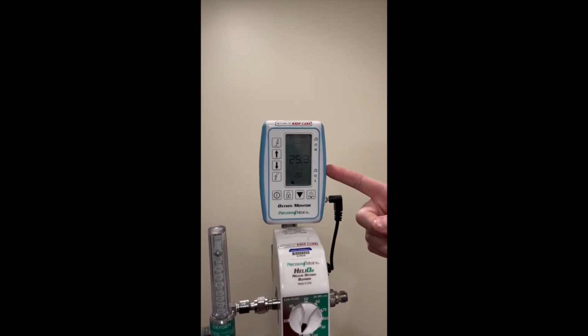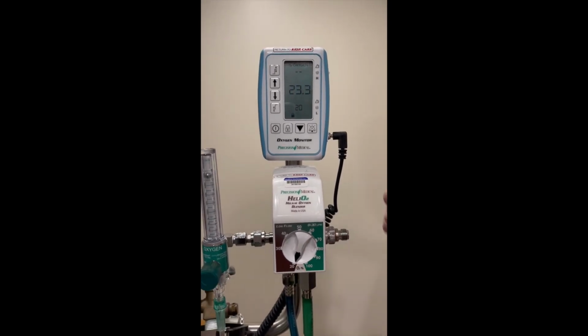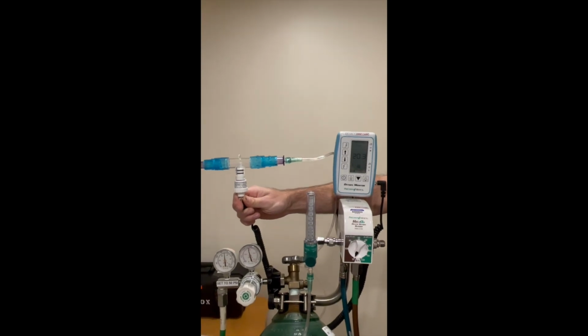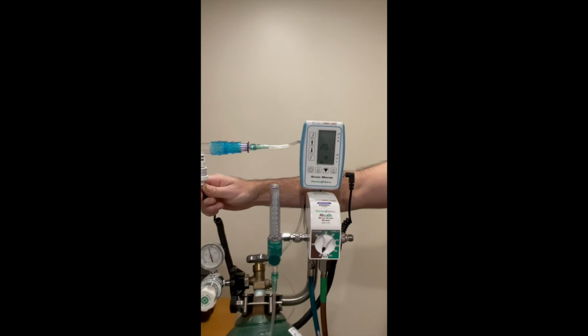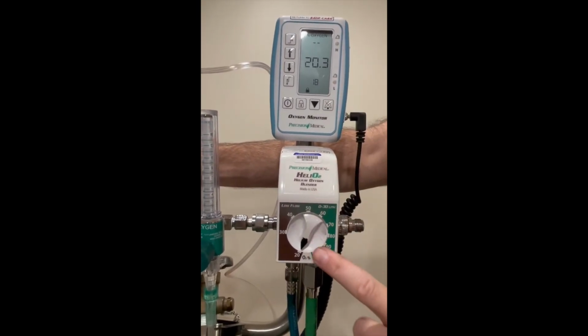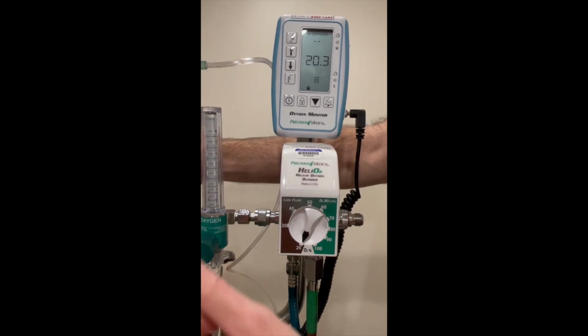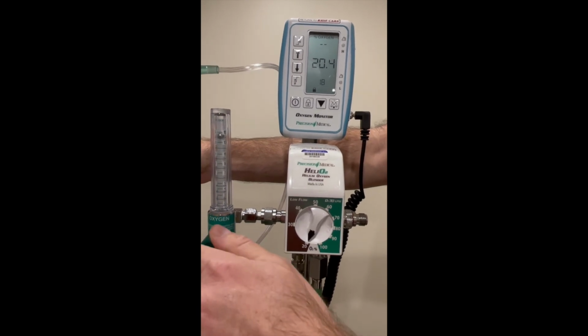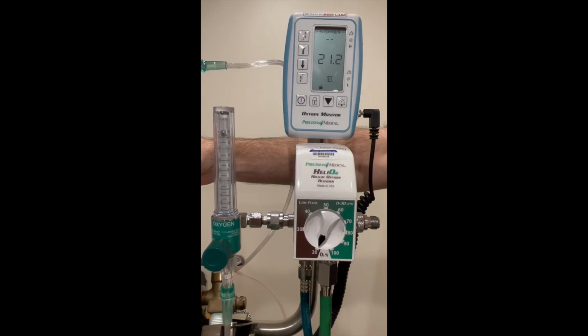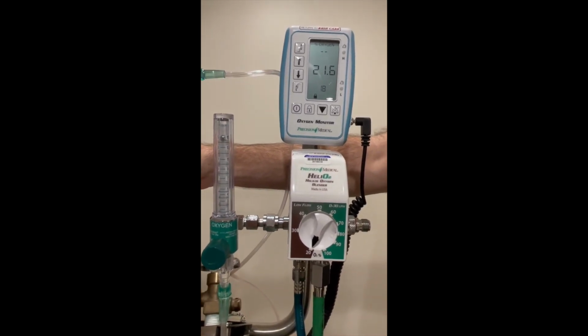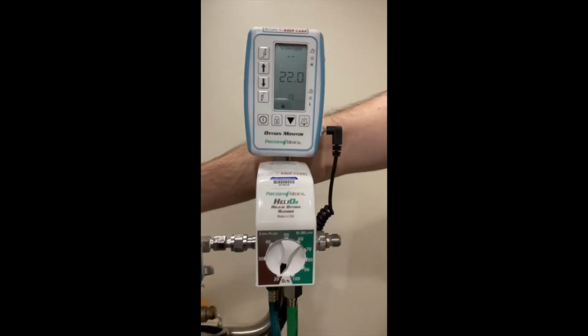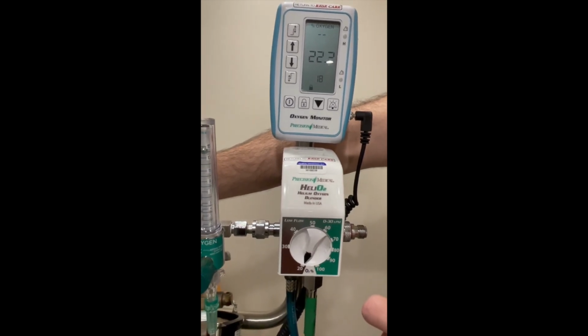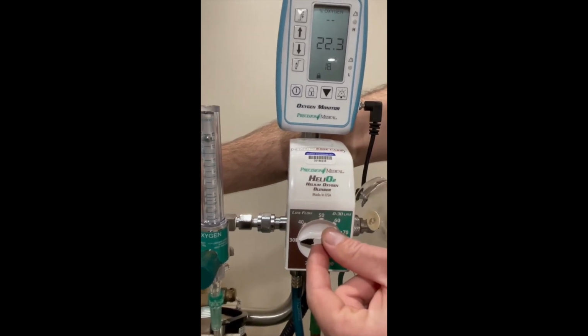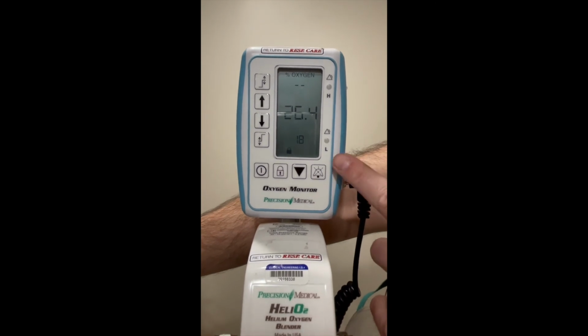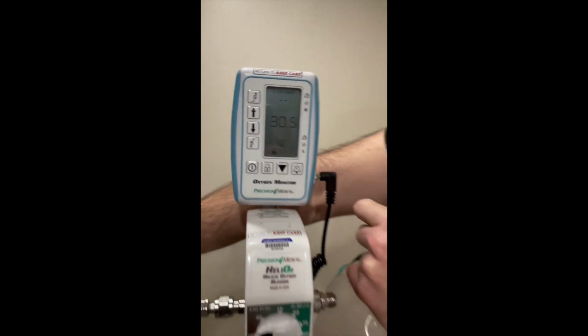You can turn on your analyzer to notate the amount of oxygen being delivered. If you want to ensure your proper dosage, either 20/80 or 30/70, we can do so here. Your blender is currently set at 20% oxygen. Let's deliver some flow and see what the analyzer shows. The analyzer shows 21.7. If your physician wants to administer 30% oxygen, 70% helium, simply move the blender to 30%. We're going to ensure that the oxygen delivery is achieved by looking at the oxygen analyzer. We are there.